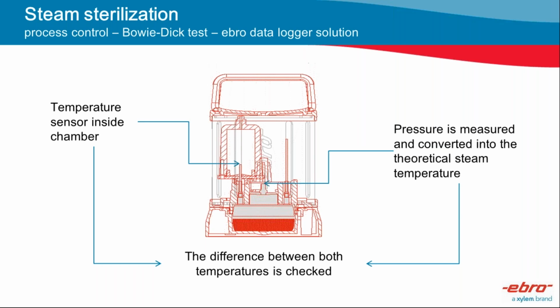Although personally, it's always nice to combine both, using the electronic Bowie and Dick test logger and the chemical indicators, because the EBI 16 Bowie and Dick test logger does more. It gives you a digital archive for complete record and documentation, and it's helping you to avoid transcription errors from using Bowie and Dick chemical indicator results. And it can also perform leak test. It can give you some sterilization parameters and even F0 value. So it's really a good product. I'm so excited to use this more in the sterilization validations.